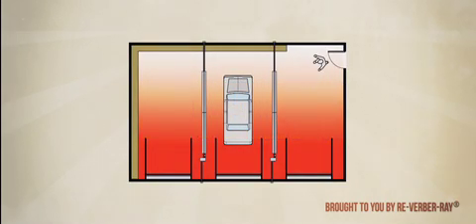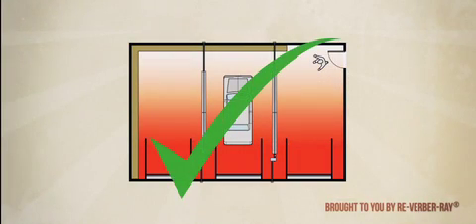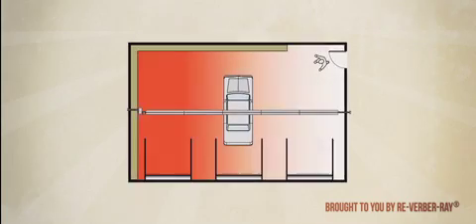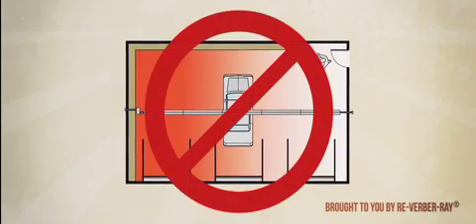Another important element to consider is placement. The heater should be placed strategically and focused in the areas of greatest heat loss. With low-intensity models, placing the hotter end of the heater in cooler areas of the building also helps achieve better heat distribution.